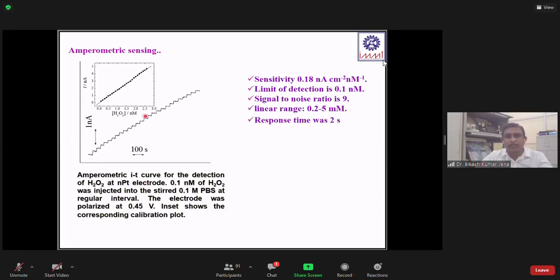With this amperometric sensing technique and the platinum modified electrode, we were able to detect sub-nanomolar concentrations of hydrogen peroxide, which is very below nanomolar concentration. So this will be very good for sensing very low concentrations in oxidase-based enzyme sensors.